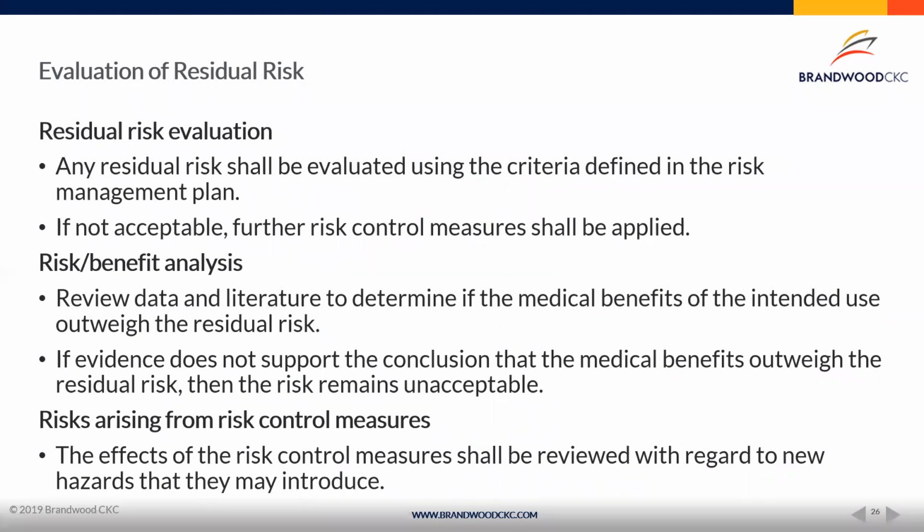From here, you make your risk-benefit analysis, you review the data, you can review literature as well to ensure that you have met the requirements of more benefit than residual risk. If you can't support that conclusion, then the risk remains unacceptable. And again, you're going to have a hard time with a regulator. And frankly, it's not a really good business decision to put devices out there where you can't reduce the risk to be less than the benefit of the device.